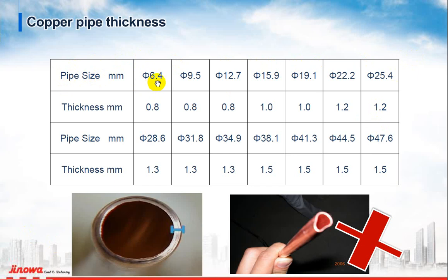For sizes from 6.4 to 12.7mm, select copper pipe thickness of 0.8mm. From 15.9 to 19.1mm, select thickness of 1.0 millimeter. For pipe size 22.2 up to 25.4mm, select 1.2 millimeter thickness. For pipe sizes 28.6, 31.8, and 34.9mm, select thickness of 1.3 millimeter.